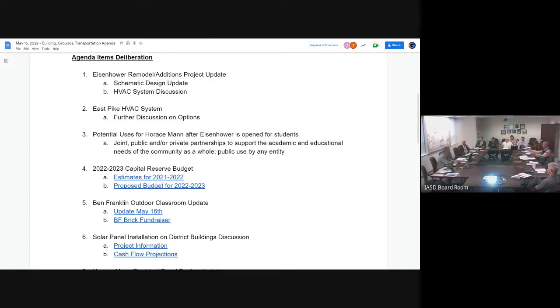Could those units be put right behind the building on a concrete slab, if we didn't want to take up floor space in the rooms? That's correct, but I'd prefer indoor units because they last better and are more efficient. You could build a closet outside the classrooms if you wanted, or do little bump outs - more expensive, but not enough to sink the ship. The closets would be about 3.5 by 5 feet, so about 15 square feet out of the classroom.